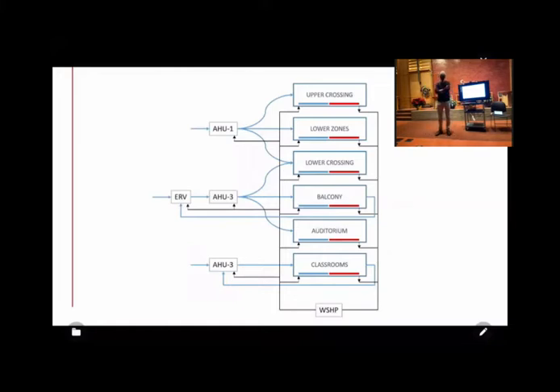And then the hot water is going to come right back to the heat pump and the heat pump's going to switch off. We had a suspicion that would happen because that precisely same thing happened at the Aldo Leopold Legacy Center. We solved the problem up there by putting a big thermal storage tank in between. It wasn't radiant floors at Aldo Leopold, it was just baseboard radiators, but the same problem occurred. Under low load circumstances, the radiators weren't kicking off very much energy and the water came back to the heat pump hot and the heat pump said, whoa, can't do it.